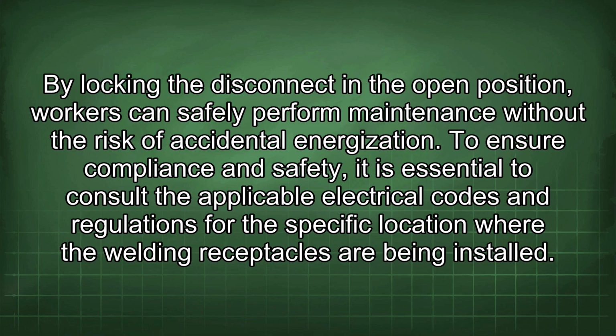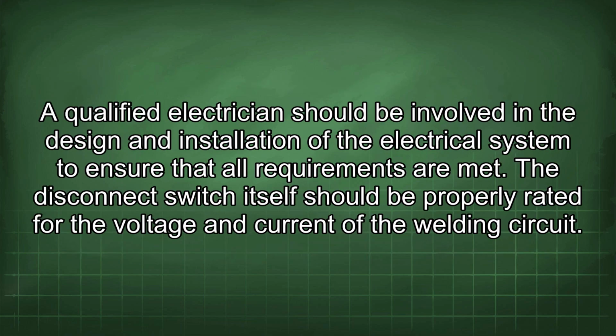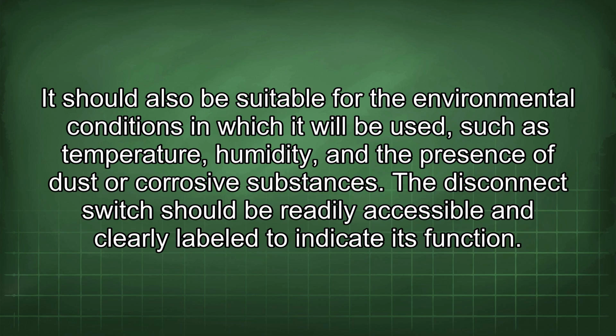To ensure compliance and safety, it is essential to consult the applicable electrical codes and regulations for the specific location where the welding receptacles are being installed. A qualified electrician should be involved in the design and installation of the electrical system to ensure that all requirements are met. The disconnect switch itself should be properly rated for the voltage and current of the welding circuit. It should also be suitable for the environmental conditions in which it will be used, such as temperature, humidity, and the presence of dust or corrosive substances.